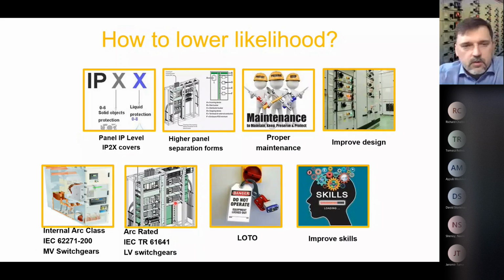We might have low voltage switchgear as well. It's a different name. It's not internal arc classified, but I think it used to be called arc resistant. Now it's, I think, arc rated. Doesn't matter. It's the same concept. Under technical report 61641, so you still can build the low voltage switchgear, which will be resistant to internal arc.